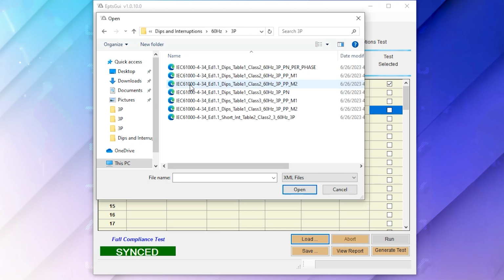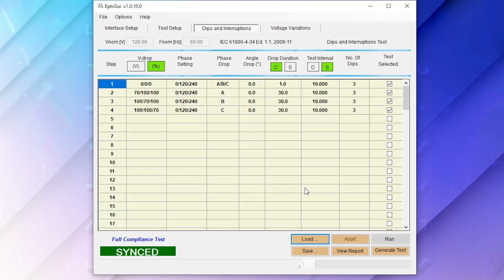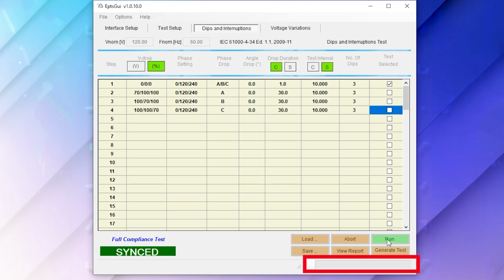3-phase. And let's go ahead and select the first routine for table 1, class 2 at 60 Hz. All right, as you can see, the criteria loaded in. Let's go ahead and run the first step of this routine by unselecting the remaining steps 2 through 4. And now let's select run. Shortly here, you should see in the lower right hand corner a progress bar shown. Let's let that progress bar go all the way across, and let's complete the test.